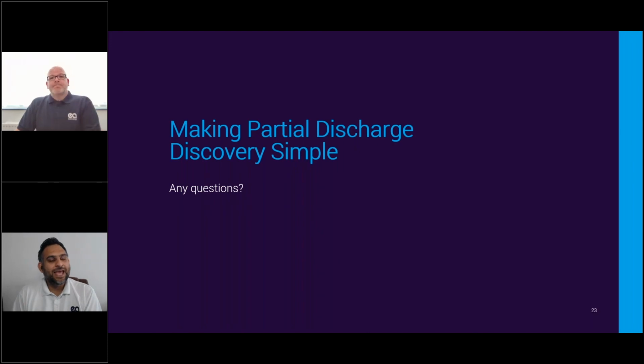That's a good question. I suppose it depends on the extent of the damage. Sometimes with surface PD, cleaning the effects of PD and making sure the root cause is addressed, whether that was phase cables being too close or improving the environmental conditions, will help in reducing any future effects of PD. Unfortunately, surface PD, once it starts, unless you do something about it, is not going to go away. If you were to leave it as it is, it will continue to cause damage until it leads to a failure. So jumping straight to component replacement might be a very expensive thing for asset owners. Cleaning can help, but it depends on the extent of damage that's been caused by the partial discharge activity.